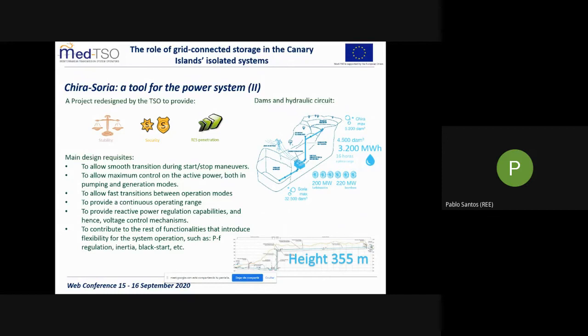There were several design requisites put in place when redesigning this project. We wanted the system to allow smooth transitions during start-stop maneuvers, to allow maximum control of active power in both pumping and generation modes, to allow fast transitions between operation modes, and a continuous range moving from maximum power in generation mode to maximum power in pumping mode. We also wanted the facility to provide all the services needed in such a weak, small, non-interconnected system: reactive power regulation, power-frequency regulation, both synthetic and natural inertia, black start capabilities, and so on.